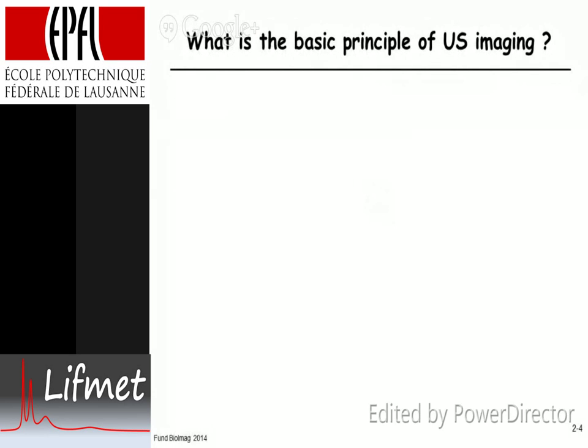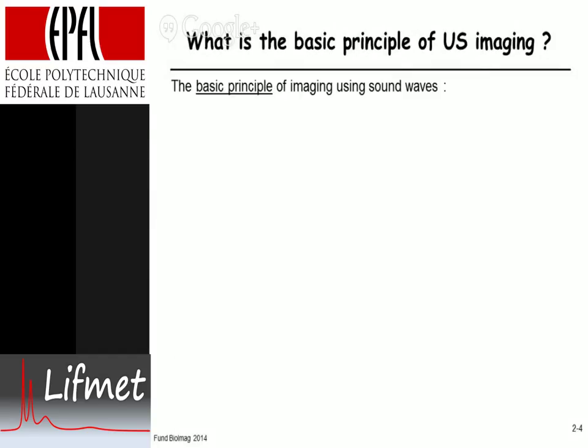The basic principle of ultrasound imaging is that you emit a sound pulse. The pulse length, which is typically one to five microseconds, has to be a multiple of the cycle time — that's one over the frequency of the ultrasound. The duration has to be long enough so that it has a well-defined frequency. If it's too short, it's the same as taking a hammer and knocking it on a table — you get the white spectrum, everything. But you want a defined frequency.